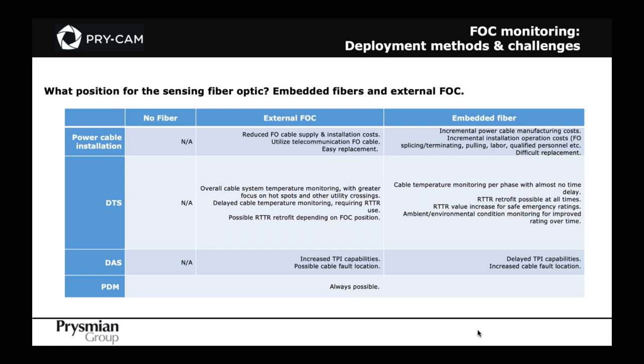As for DTS, external fiber optic cables give us an overall cable system temperature monitoring overview with greater focus on hotspots and other utility crossings. There is a delay in cable temperature monitoring requiring the use of RTTR, and RTTR can be retrofitted in most cases depending on fiber optic cable position.